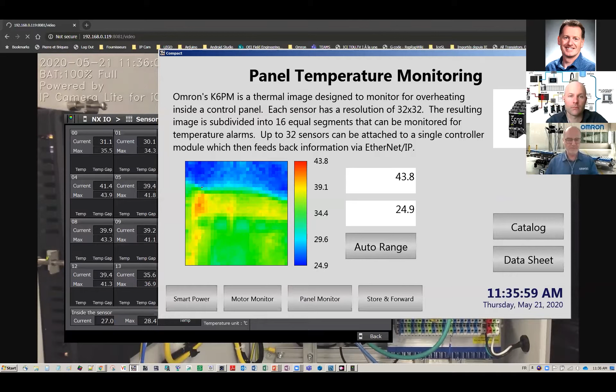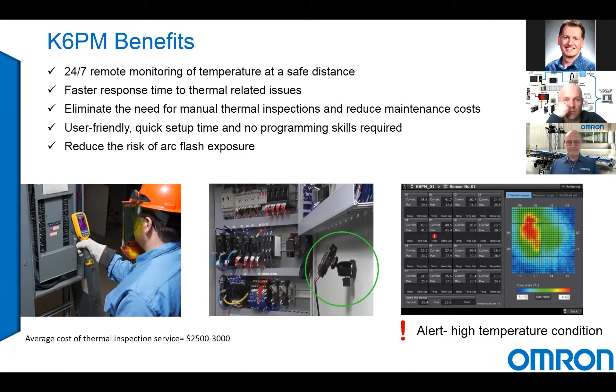The benefit is reducing the cost of your inspections, because otherwise you need to send somebody or hire an electrician to go through your control panels on a monthly, six month, or twice a year basis. Within that time span, something can happen, and it's also very costly, since he has to dress up in an arc flash suit to open your control panels and expose himself to danger. Whereas these cameras will do that in real time inside your control panel at a reduced cost, giving you an actual picture of what's going on at any given time of the day.